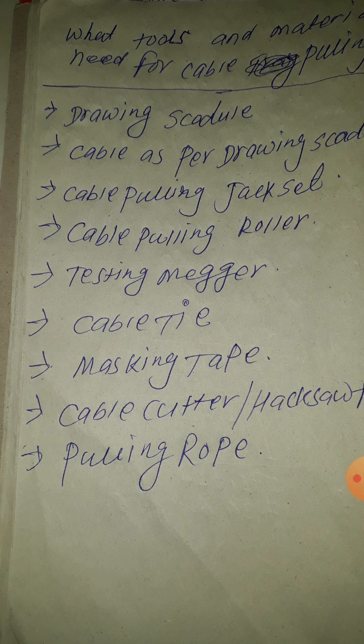Next is checking the cable as per the drawing schedule - whether the cable available matches the drawing or not. Check the cable outside insulation, where the cable sizes are written - 4 core, 3 core, or any size, which core and which size - everything is written outside the cable. So it is written outside the cable during cable pulling time. And next is the cable pulling jack set.